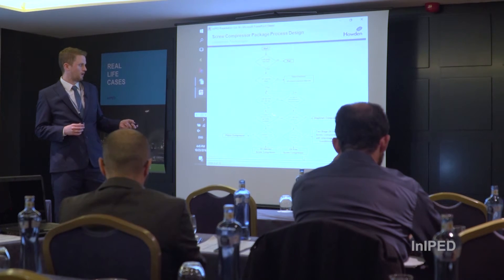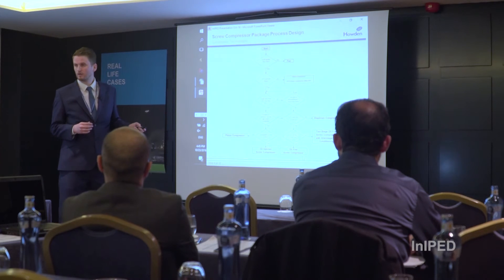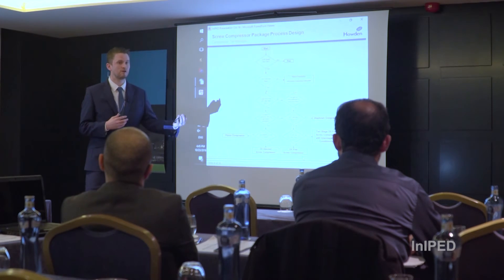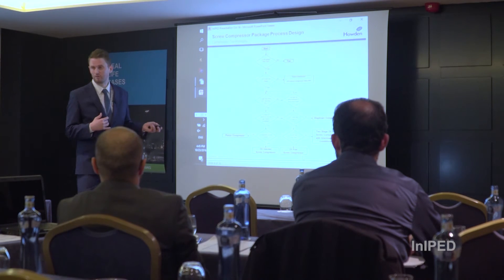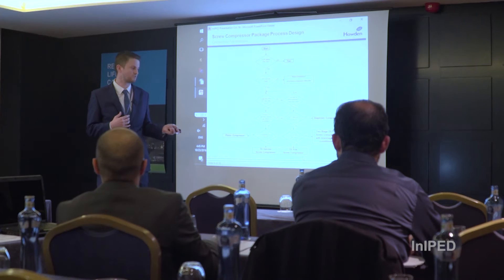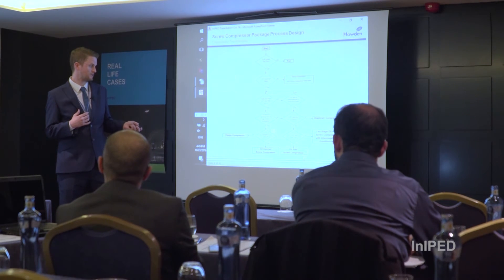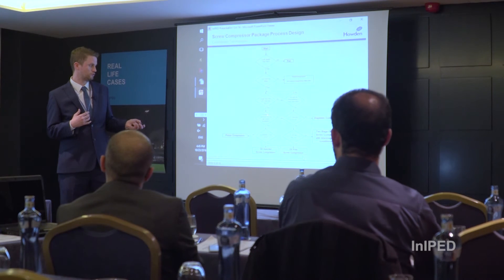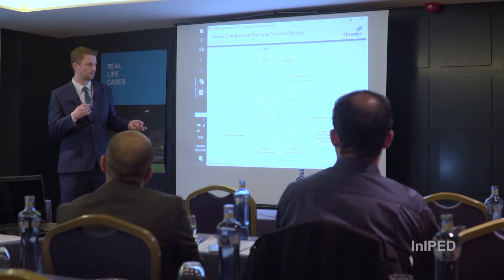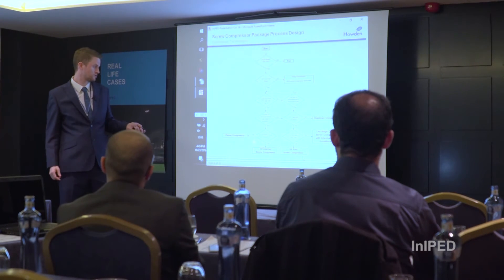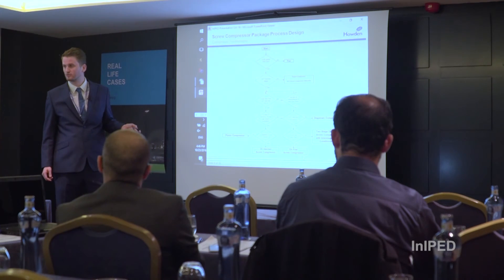The second point is around trace oil carryover in your application. You can get really efficient separation of oil and gas, but you're never going to get 100% separation. So you're always going to have a little bit of oil in your discharge gas. If that isn't acceptable, then you really need to go down to the oil-free screw compressor applications; otherwise, you can utilise your oil-injected screw compressor.